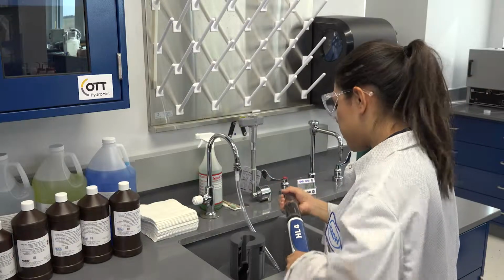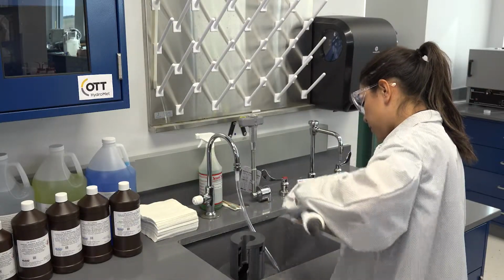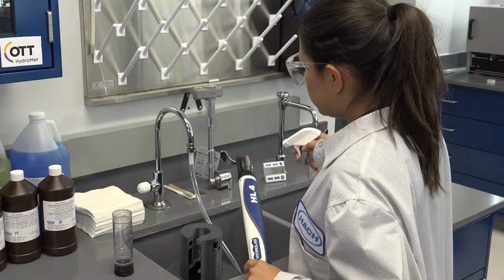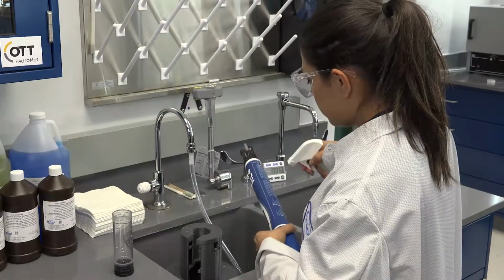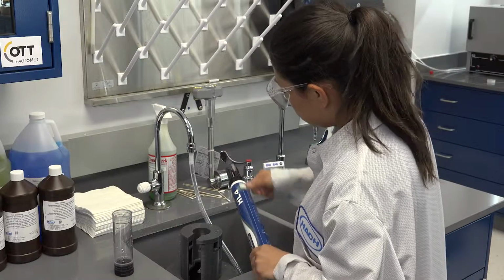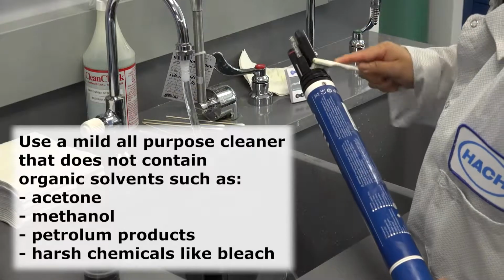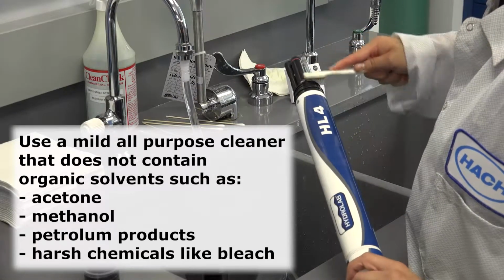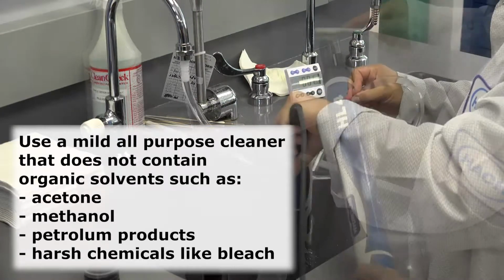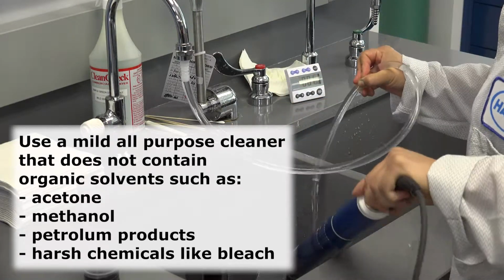The conductivity sensor should be regularly cleaned because debris, organisms, and other contaminants in the sensor cell will have a negative impact on the accuracy and stability of the readings. If deposits on the sensor are difficult to remove, soak the sensor in warm, fresh water until the deposits soften. Never use organic solvents such as acetone or methanol on any part of the sensor.